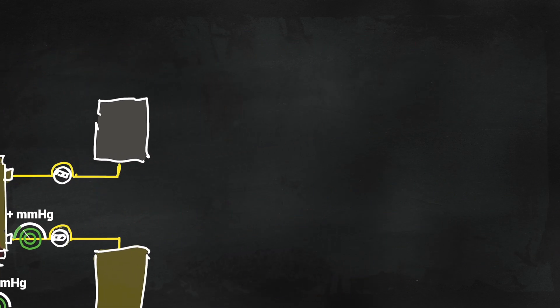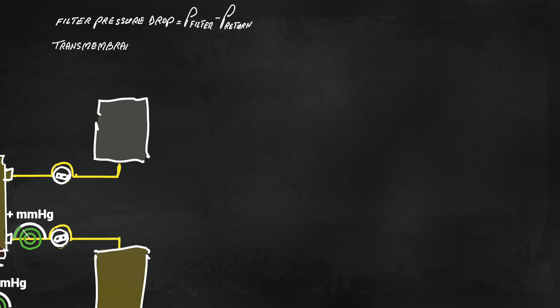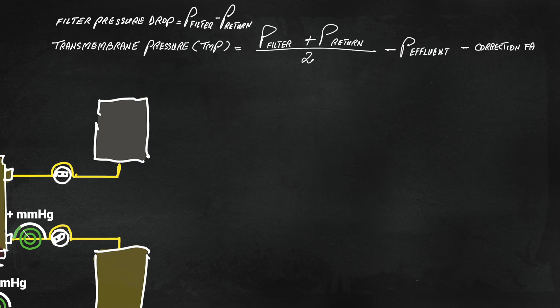You can use the filter and return pressures to calculate filter pressure drop, which represents the average pressure on the blood side of the membrane. Then subtract the effluent pressure from the dialysate side from the pressure drop. Then you'll have the transmembrane pressure.